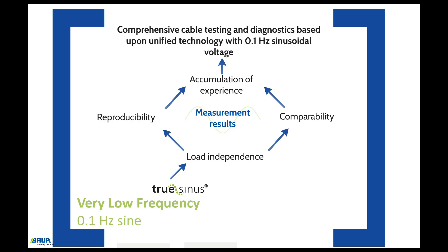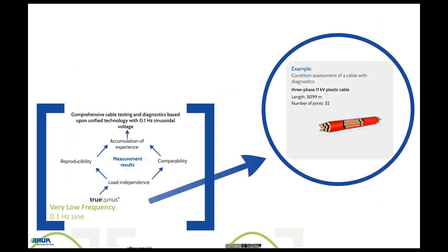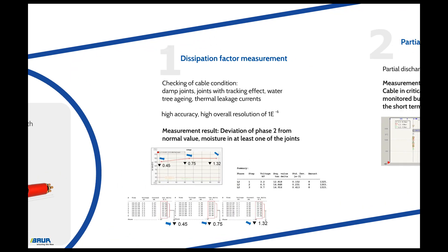Comprehensive cable testing and diagnostics is therefore based upon one unified technology with 0.1 Hz sinusoidal voltage. Let us take a look at the benefits and significance of the measurement methods based upon 0.1 Hz sinusoidal voltage using an example. The condition of a three-phase 11 kV plastic cable is to be assessed with the aid of cable diagnostics. The cable is about 3 km long and has 32 joints within this route. The dissipation factor measurement performed at the beginning supplies information on the general condition of the cable, allowing damp joints and joints subject to the tracking effect, water tree aging, or thermal leakage currents to be detected.